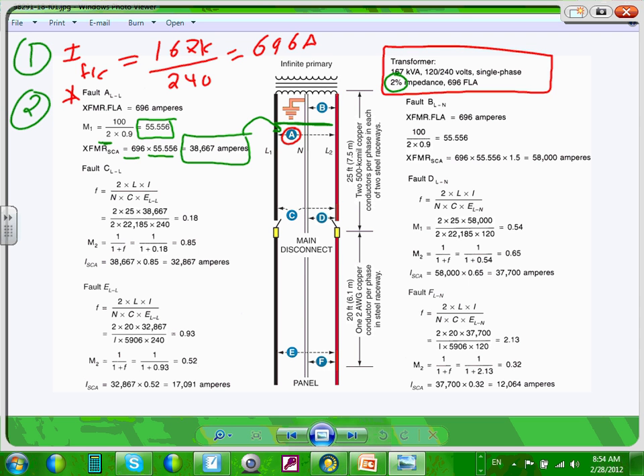If I go short these together, here's the available short circuit. Any question? Right at the terminal of the transformer. Piece of cake. We've done it before, guys. You take the full load current and divide it by the impedance. This is what they did.